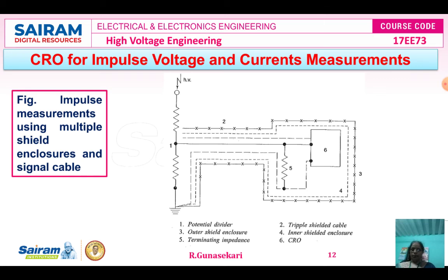So another important factor is the layout of the power and the signal cables in the impulse testing laboratories. Power and interconnecting cables should not be laid in a zigzag manner and should not be cross connected. All power cables and control cables have to be arranged through earthed and shielded conduits. This arrangement should provide for branched wiring from the cable tree and should not form loops.